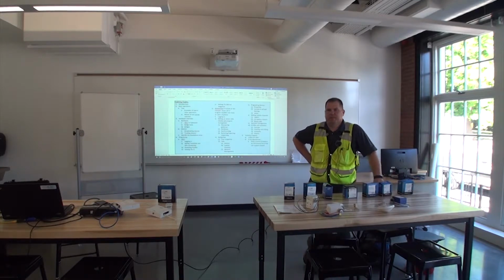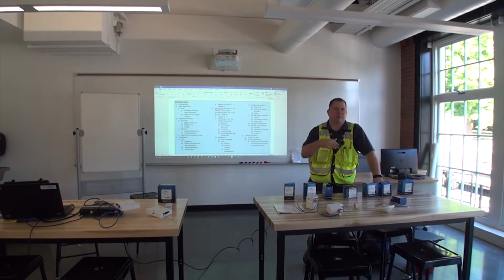So if you had a lamp in the room plugged in there, you turn the light on, at the same time you turn anything else off. Technically we don't wire it up to the manual control switch, it's just connected to the occupancy sensor, because Title 24 and WSEC, Washington State Energy Code, says that 50% of all outlets in a space have to be plug load controlled based off occupancy in the space. It's the only reason we put them in.